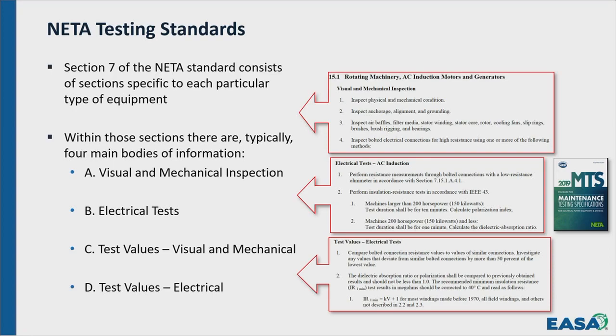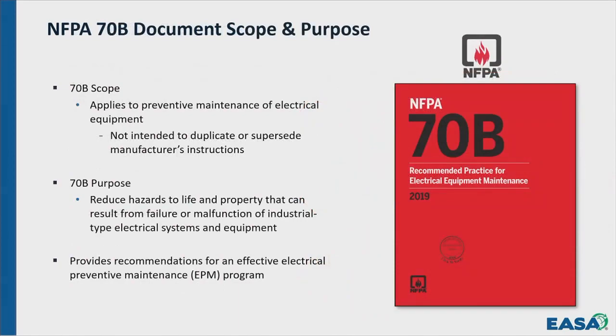Some of it is just pass-fail, if that's the criteria for the test. But for tests with definitive results, there's a specific expected result—polarization index has one, dielectric absorption ratio has one—and those results will be in there too. So you can do the electrical test and see the expected results. Great guidance for what to do in the field from a maintenance or acceptance testing standpoint.